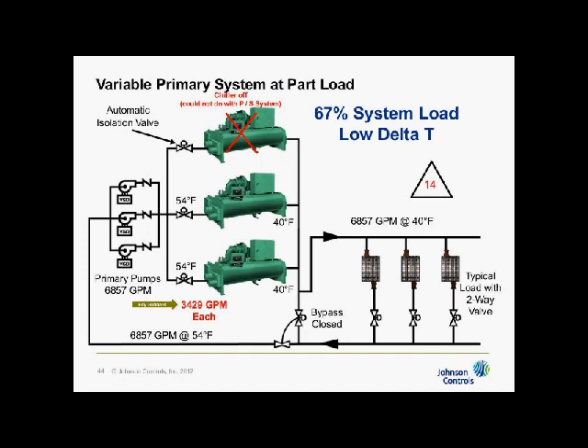Just overpump these. And can I overpump them? Of course I can. Chillers can handle up to 11 or 12 feet per second. Typically designs are around 5 or 6 feet per second. The design for the chillers that we pick for this example that we run calculations on later is at 5.8 feet per second, and you can turn it down to 1.5. Okay, and you can go up to 12, as long as you don't exceed the max pressure drop through the water boxes, which for these chillers, that are 2-pass, is 45 feet.